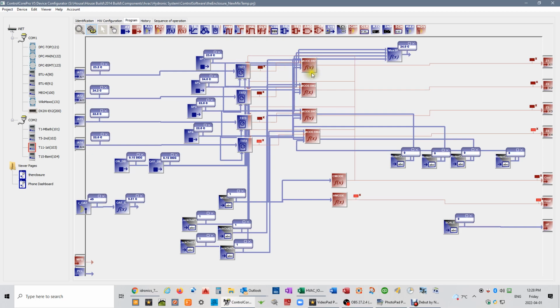So the next one is some further logic that's been built in. So let's go to T-stat 4. That's the downstairs bathroom. It's against the garage, so it's always cold because the garage is not heated yet and not insulated. So it often actually has problems maintaining its set point because of the missing insulation.